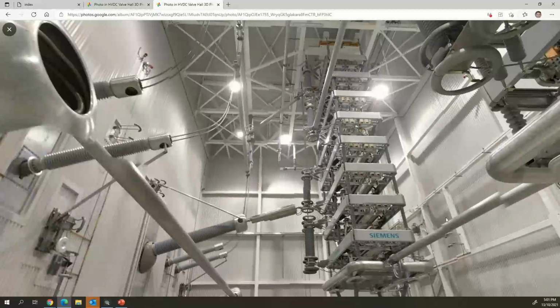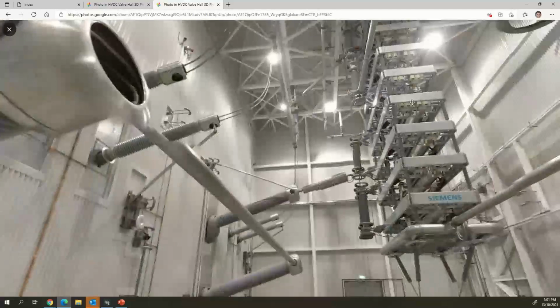Yeah, the high voltage on the bottom. You've got your, you know, this is your star connected coming into your high side 6-pulse converter, then you've got your low side 6-pulse converter that's connected on the delta, and then the neutral on the top, and repeated for each phase. Yep.